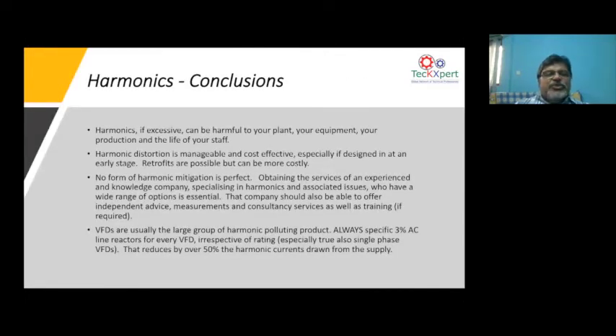Next. So it is harmonics, if excessive, it can be harmful to your plant, your equipment, your production, and the life of equipment, and it's a safety issue. If it is managed well, it can be very cost effectively handled. Retrofits are possible, but sometimes can be more costly. So you need to see what is the right way of mitigating it. No form of mitigation is perfect. So you need to have the right experienced people to look in and advise you how to go for mitigation options. And VFDs are a group of harmonic polluting products. So make sure proper line reactors are used so that the active filters can effectively work. Go to the next.